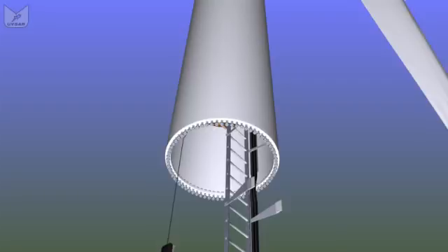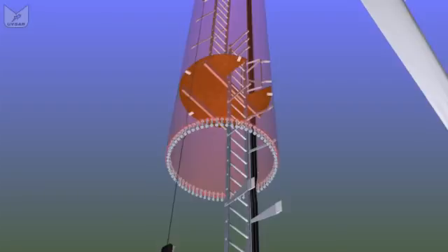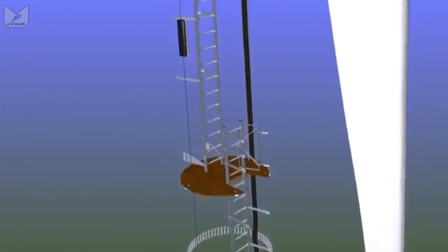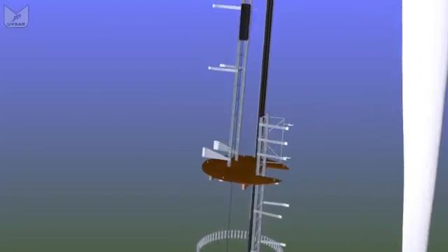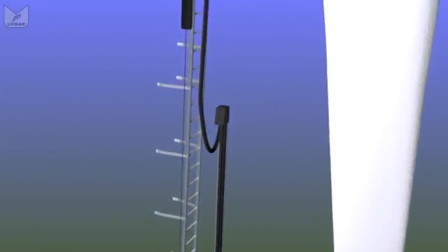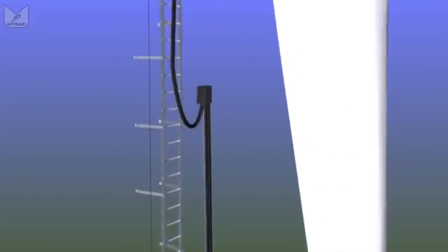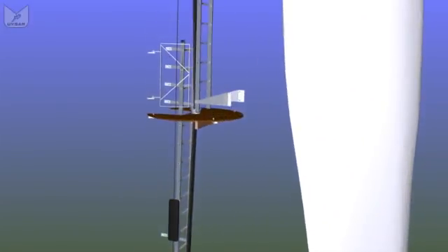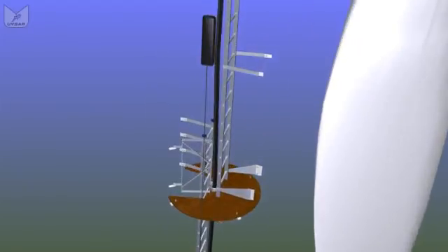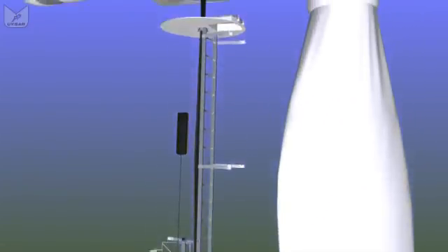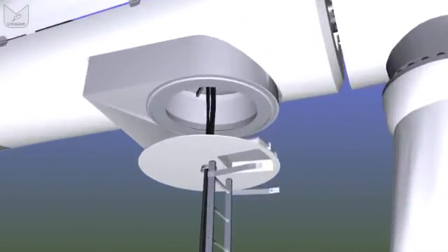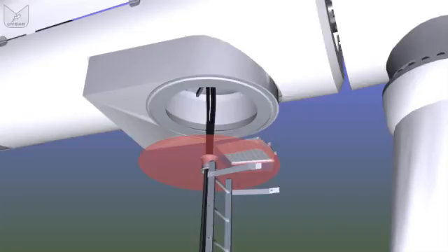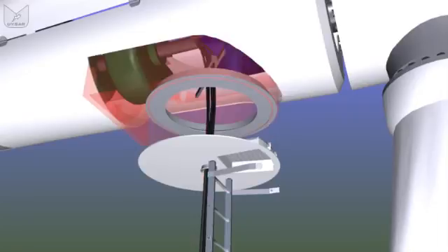But as we move higher and higher through the platforms, they're getting slowly narrower and narrower, so the ladders are getting a little bit closer together. But eventually the main cables stop being attached to the wall and they hang freely in the center of the tower, so they can twist as the nacelle rotates to face the wind. If they twist too many times, the nacelle will spin itself around to remove the twists. As we move up, the cable goes through a hole in the center of each platform, and at the top of the tower we have a steel platform with a sealed trapdoor, which we call the yaw platform. Just above that we have the yaw ring with the bearings that allow the nacelle and the rotors to rotate around to face the wind.